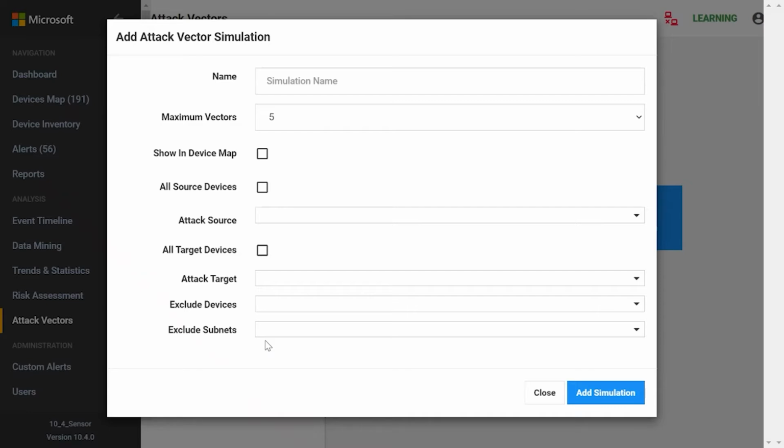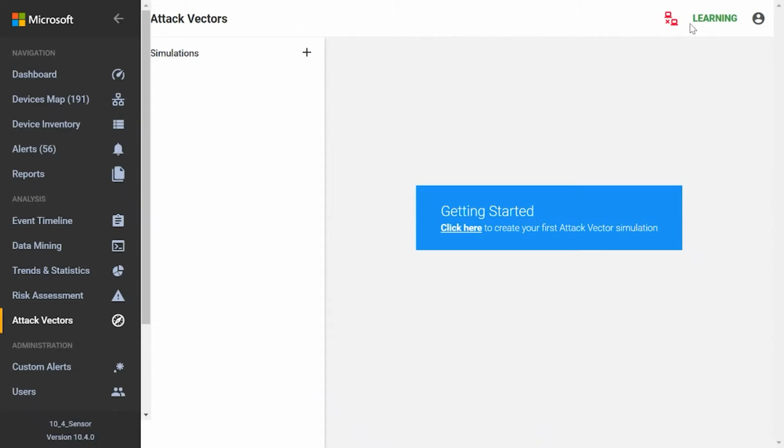Obviously, it has to be IP for this to get back out onto the internet. So what we're finding, at least for some customers that we've been talking to, is the ability for a nice threat event to be picked up on is a device successfully connecting to the internet. There's also things like reprogramming firmware and stop commands and all the standard stuff, but a nice one for us at least in this modern world is if a device is being successfully connected to either through a proxy or through a poorly configured firewall, then we need to know. So I did have a couple of ones I'd run earlier in here, but it looks like the demo gods have slightly switched that one off, but at least it gives us an idea of what's actually available.